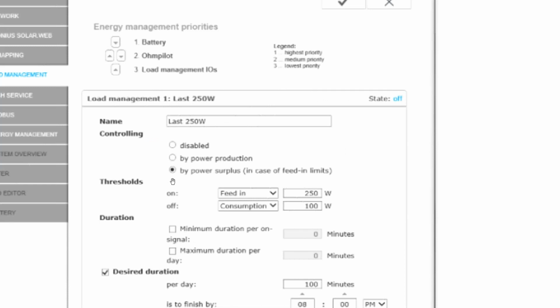We want to control this by surplus, and this is a very good option when you have feed-in limits, so that in most African countries, we are not allowed to feed PV power to the grid, and therefore it's a very good idea to look at how you can utilize all the energy that you're generating. And one of the ways is to now assign these thresholds.